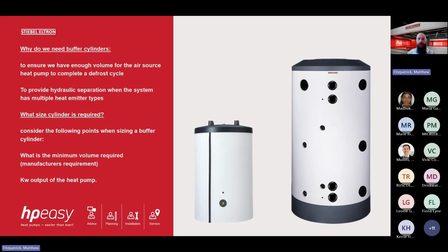So as an example, the buffer cylinder on the left-hand side is our SPP 100 Classic, so it's a 100 litre buffer cylinder. And on the right-hand side is our STH 720 Plus, which is a 720 litre buffer cylinder. In the example of the 89 kilowatt ground source heat pump, trying to deliver 259 litres per minute through a cylinder, which is half this, or more than half the size of the volume coming from the heat pump per minute, it's just not going to work. It's going to cause problems and faults because it will restrict the flow. And we have the backlog of energy. So then a larger buffer cylinder would be better suited, larger tappings and a larger volume to allow it to transfer through to the heating system.